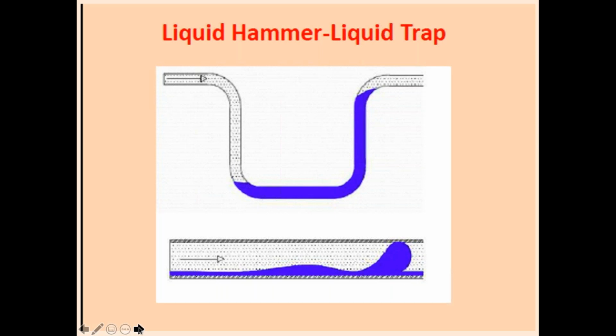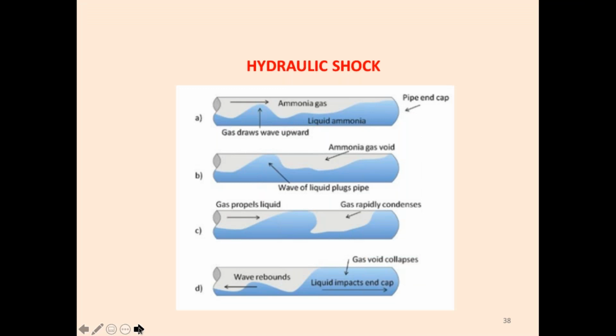Then don't provide loops in the liquid line. I have seen many places in wet return line, especially from LP vessel back to compressor, the piping is with several loops. Loops can cause big problems: liquid hammer, liquid trap, and big problems. I will explain in the next slide what happens. Very important slide: hydraulic shocks. A lot of people, 80% of people, complain that when they use pump circulation systems, there are heavy vibrations in their plant. Why does this happen? Because the pipe is flowing with liquid plus ammonia gas, and the gas, its density being lower, closes the pipe, and when the pipe gets closed, the gas gets trapped.